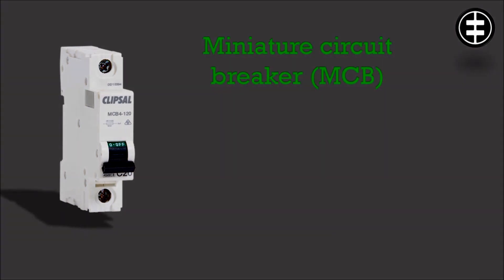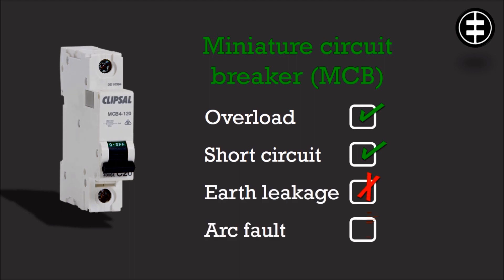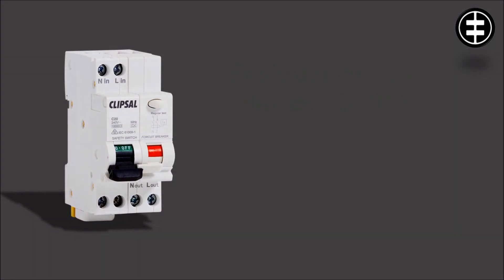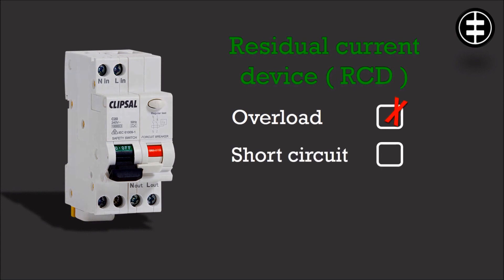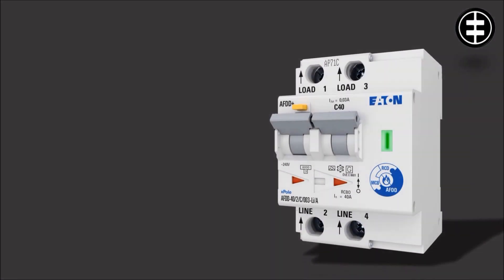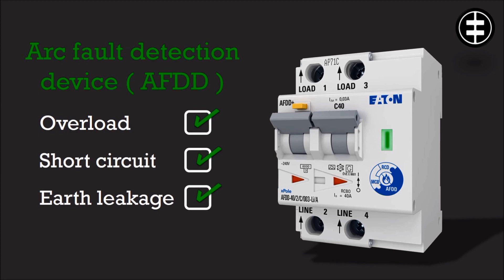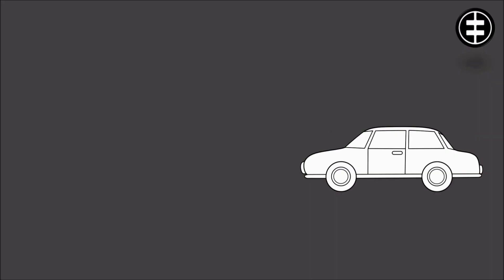Arc faults cannot be detected by common protection devices, because the arc current is normally lower than the rated and short circuit currents — miniature circuit breakers cannot detect the arc fault. Furthermore, residual current devices are unable to detect arc faults because arc faults do not create any earth leakage current. The recommendation is to use arc fault detection devices to protect electrical installations, buildings, and people from fire caused by arc faults. These devices are able to detect overload, short circuit, earth leakage current, and arc fault, and should be used in all buildings across a wide rated current range.